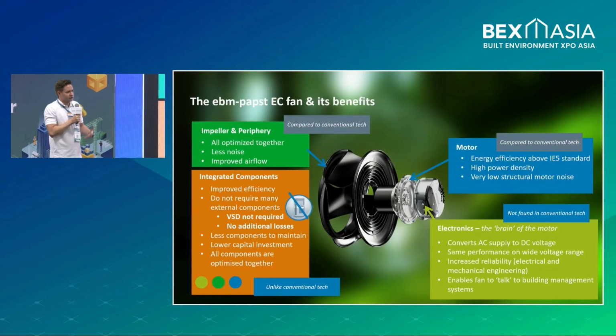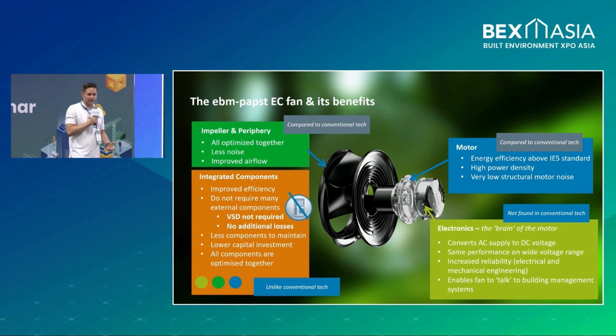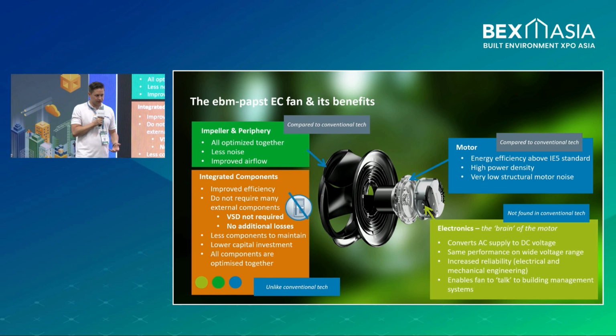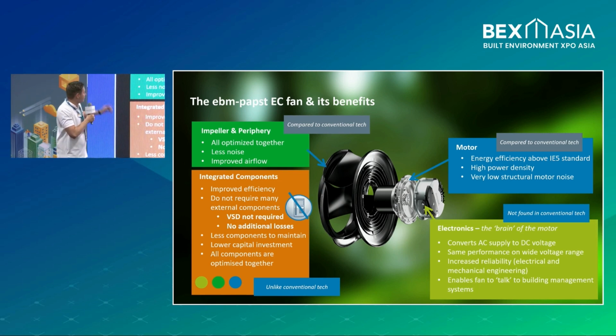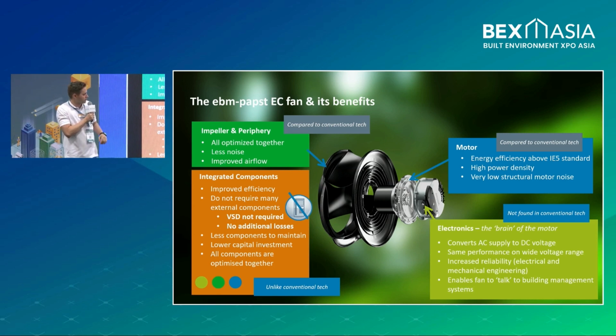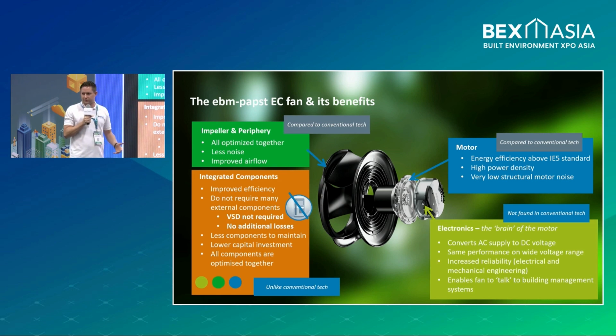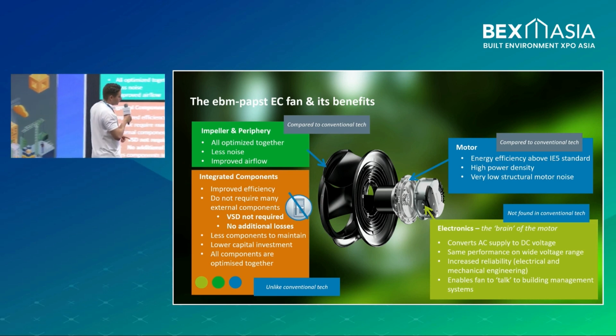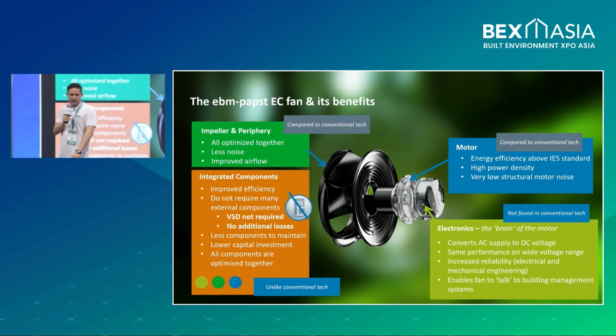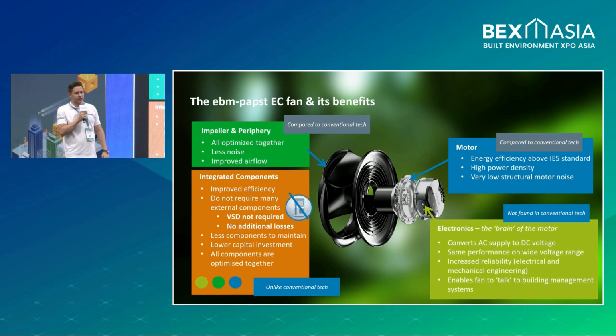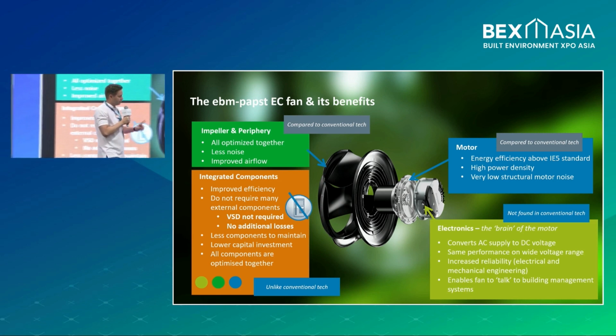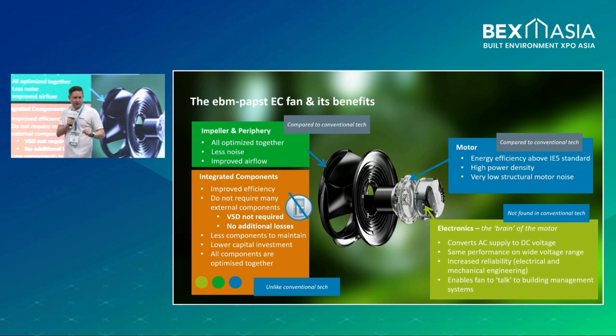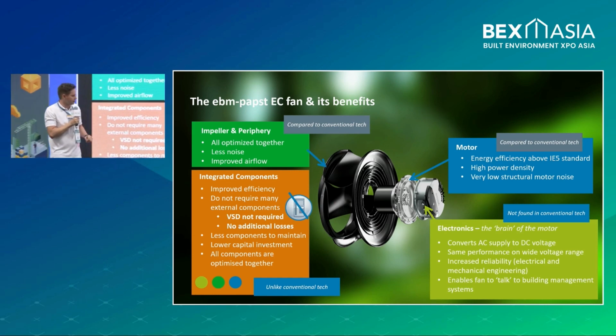So what does EC technology mean in the name ebm-papst? When we talk about EC technology, we're not just talking about electronics — it's our complete way of thinking. It means developing a fan with all components optimized together: from the aerodynamics, where the impeller and all the periphery are optimized completely together, to a motor above the IE5 standard and above all efficiency targets available in the market, which is very compact with high power density. Due to our outer rotor motors, it's much more compact than internal rotor motors, has very low structural noise, and comes with the brain of the motor, the electronics, already equipped. The electronics are designed, developed, and produced by us.